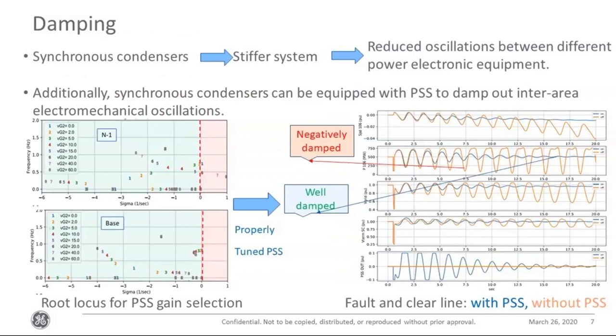This slide is about damping, and that might be something that Fred might find interesting. So generally, even without PSS, because synchronous condensers are leading to a higher short circuit strength and a higher inertia, it causes your system to be stiffer, which generally can help reduce the oscillations between different power electronic equipment even without a PSS. And traditionally or typically, synchronous condensers are not equipped with PSS because they do not have a participation in the active power. The only active power interaction is primarily what they absorb for covering up for the losses.